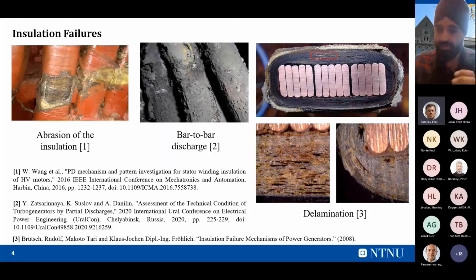Another point is that the entire winding is kept in a particular slot of the stator of the hydro generator. Due to the mechanical movement of the stator, there might be a chance of abrasion around the outside surface of the insulation. That will also cause deterioration, which will further lead to breakdown of the machine. And if the gap between two nearest bars is small, there might be a chance of bar to bar discharge. So these are the reasons which will ultimately lead to the failure of the insulation.